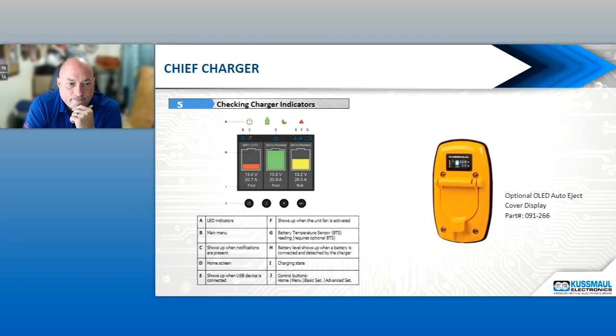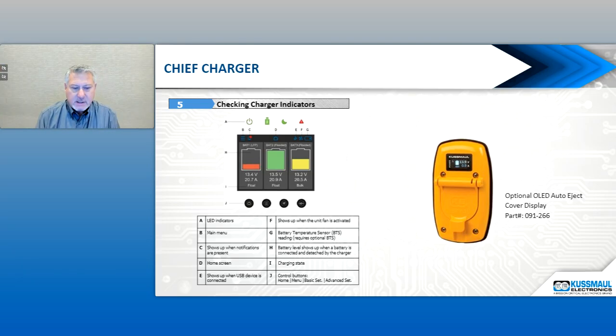Yep, that's correct. Thanks, Danny. And something else real quick, just on the display itself, it will indicate if it is seeing an actual problem. If you look at where it shows notifications, it will display an error message, and also there's a low red warning light or caution light. If that is on, and if you see a message like an E10 or an E04 error, that is an indication that there is something wrong with that charger, and you need to contact Kussmaul to get that replaced. It's something that's gone wrong, or something internal, or it might be incorrect on the charger itself.